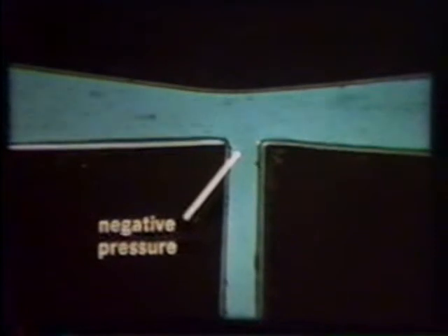In a pipe system, velocity is restricted, and part of the potential energy remains as pressure. Because water is incompressible, the pressure forces velocity to increase as a pipe becomes smaller. A tapered pipe allows a gradual and more complete changeover from pressure to velocity. As velocity increases, pressure falls, and negative pressures may develop along the sides of a pipe. This principle is often used in suction devices, or to introduce additives in fire streams.